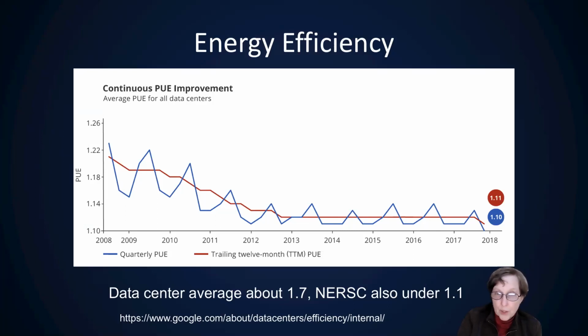One big advantage of running a data center in Berkeley is that you can use free outside air cooling, since it stays fairly cool there, aside from some hot summer days. On those hot days, the cooling at the center relies on cooling towers, using evaporative cooling. Since Berkeley is usually dry when it's hot, evaporative cooling works very effectively.